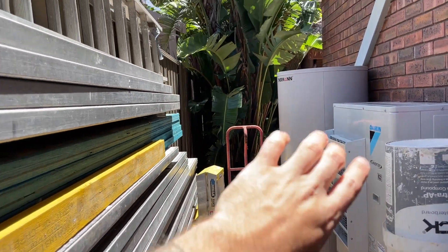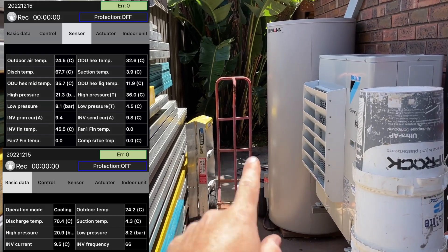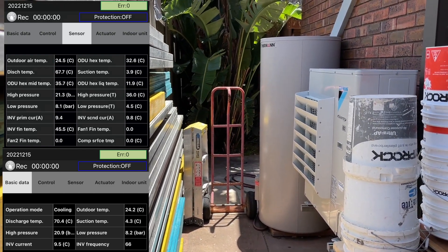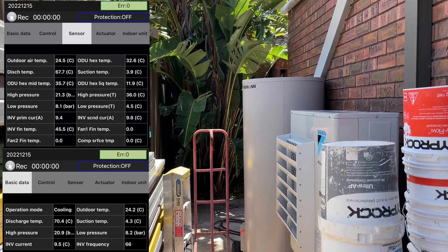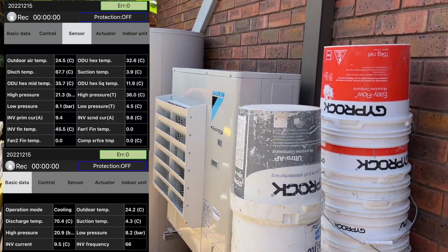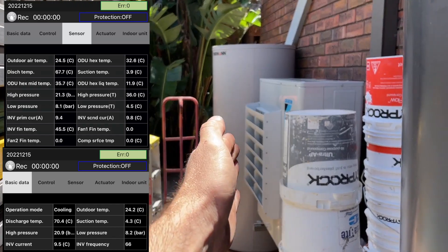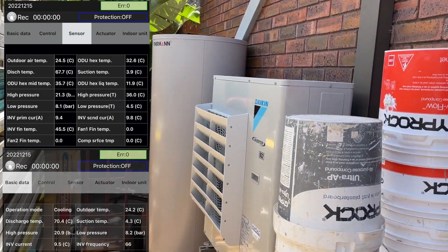That's fully ramped up now, gone through test mode, and honestly it is roaring at the top — barely anything there. It's smashed through that hot air, it's just going. Even though it complies with the Daikin spec, I don't like it going bang trying to get it out. Should give Actron a go — there's one that's a top discharge which is epic, it's so massive. What's everyone's thoughts on that? Installing it in pretty much every house you go to, the fence is right in front of the aircon — makes you wonder why they make it front discharge. It's pretty stupid really.